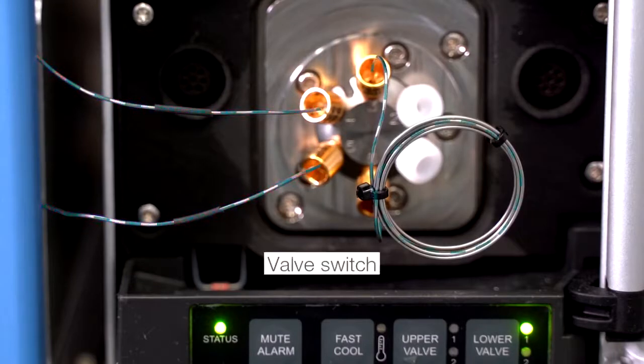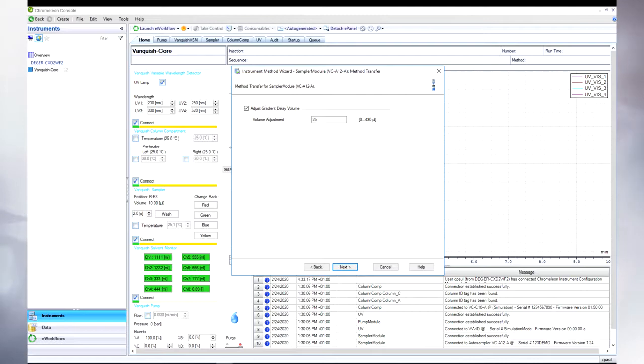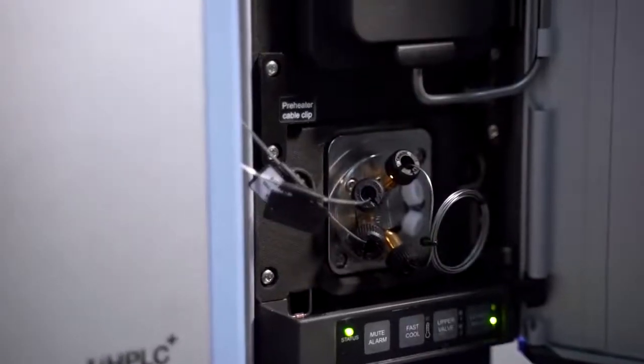We are introducing the Thermo Scientific Vanquish Core HPLC system. This is very exciting, because it empowers HPLC analysts to do method transfer faster and easier. For this purpose, we designed a system that allows to seamlessly adjust the gradient delay volume, by installing two separate flow paths as well as making use of the metering device of the autosampler. The latter one is usually only used to aspirate the sample, but we can also use it to fine-tune the gradient delay volume on a microliter scale. In total, this allows us to adjust the gradient delay volume over a wide range, without any modifications to the gradient table.